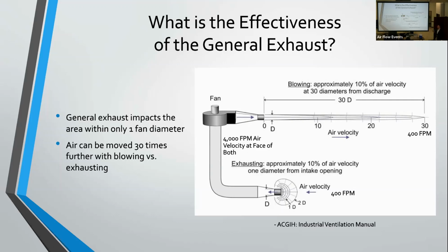So if you consider blowing the air like I just showed you with the birthday candle, rather than 1 fan diameter, you're actually able to impact that area by 30 fan diameters just by blowing that air. So you're able to move that air 30 times further just by blowing it rather than trying to pull it. That's one of the main reasons why pressurization is so effective in your buildings, by blowing that air into the space rather than just trying to pull it out of the space.